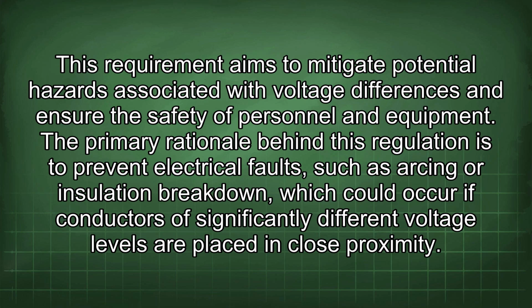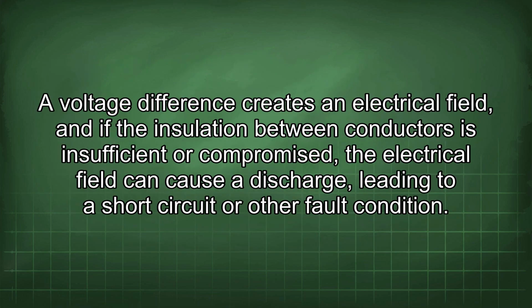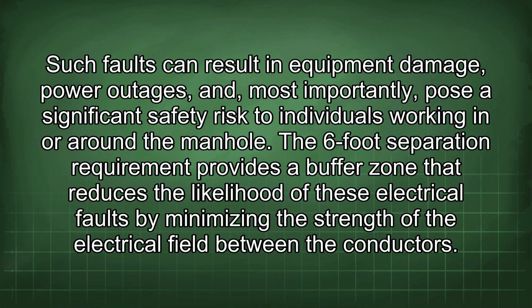The primary rationale behind this regulation is to prevent electrical faults such as arcing or insulation breakdown, which could occur if conductors of significantly different voltage levels are placed in close proximity. A voltage difference creates an electrical field, and if the insulation between conductors is insufficient or compromised, the electrical field can cause a discharge, leading to a short circuit or other fault condition. Such faults can result in equipment damage, power outages, and, most importantly, pose a significant safety risk to individuals working in or around the manhole.